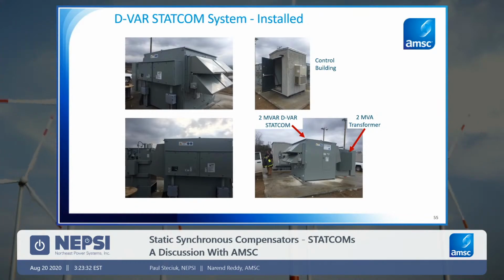There's a concrete pad that's needed for it, and both the DVAR and the transformer just sit on the concrete pad. The throat connection allows it to sit at the same height. In this particular installation, we also had to supply a control building. Obviously, this was a remote installation at a facility where there were no control buildings. So we provided that to house our master controller, plus the auxiliary supplies and things like that. And that's certainly something that we can manage depending on the requirements of the customer.